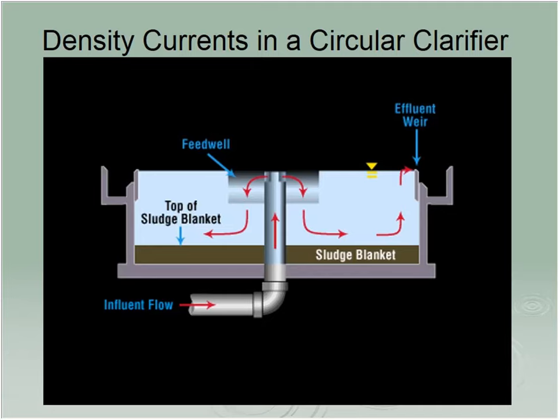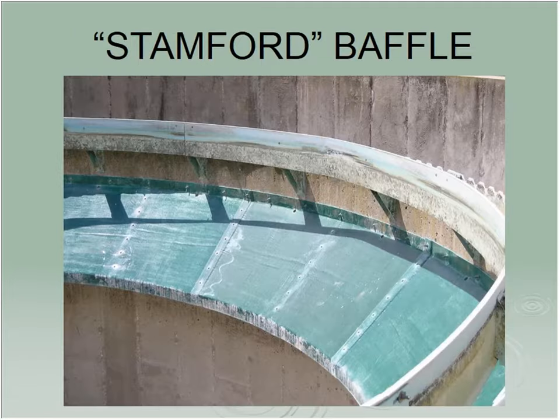Let's go back here again. You look at this, you follow the arrows. The thought is that the baffle will push it downwards, it scoots across the blanket, and then comes right up along the wall. So it really is not there for the standard detention time that you would calculate. It never is, but it's not even close. The shorter the time it is in here, the less time for things to settle, so I'm going to carry material over when this comes out.